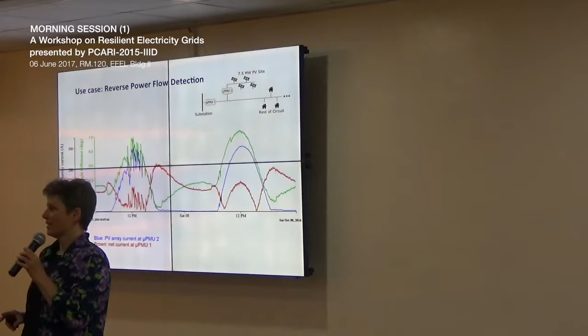Here we also show a brown curve, which is the net current at PMU number 1, at the substation. There's a really interesting thing that goes on with the net current at the substation that you wouldn't have known any other way: it changes direction. So the power flow actually reverses, and sometimes this circuit is exporting power through the substation, and sometimes it's importing power and serving loads as usual. With conventional SCADA systems, you don't know the difference—you can't tell. This can tell the difference.